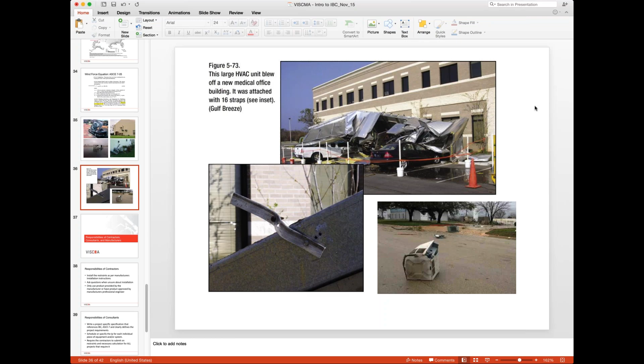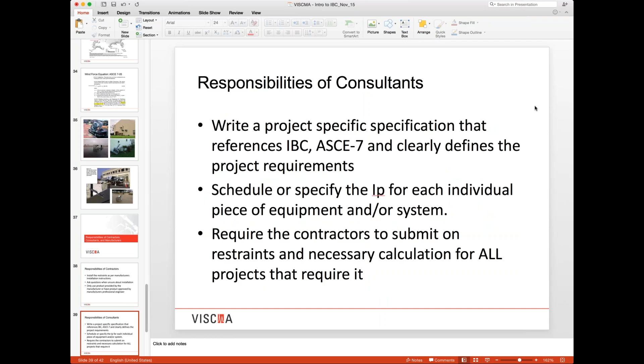The consultant also has to require the contractor to submit restraint calculations for all projects that require it, so that the building's structural engineer or their consultants have reviewed it and been alerted to the loads this equipment will apply to their structure. Often, especially with large equipment, the building engineer was unaware of the level of load the building would see from that equipment. By submitting all that information back up the chain, everyone becomes aware of the loads being applied to the building.